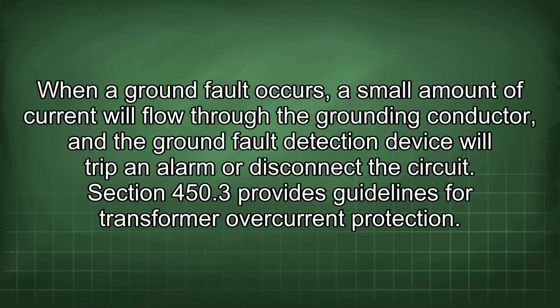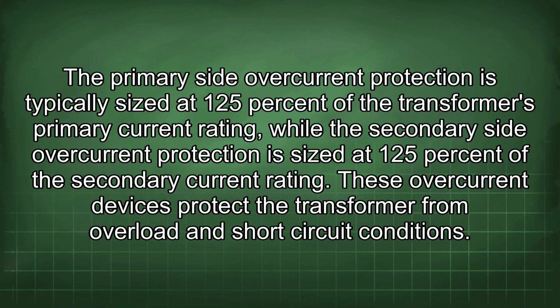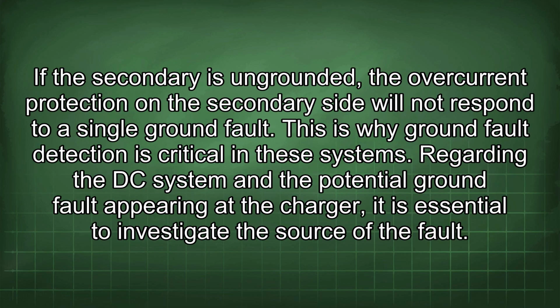Section 450.3 provides guidelines for transformer overcurrent protection. The primary side overcurrent protection is typically sized at 125% of the transformer's primary current rating, while the secondary side overcurrent protection is sized at 125% of the secondary current rating. These overcurrent devices protect the transformer from overload and short-circuit conditions. If the secondary is ungrounded, the overcurrent protection on the secondary side will not respond to a single ground fault. This is why ground fault detection is critical in these systems.